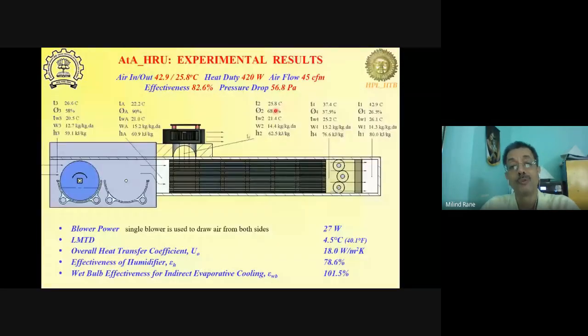Now this cooling, what we just saw here, was free, because this is simply taking the exhaust air and recovering the availability in the exhaust air using some amount of water here. Note that we have cooled down the air to below its wet bulb temperature here. Now, the wet bulb temperature of this air was 26.5, and the air being delivered is 25.68 degrees centigrade in this example. So that's why the wet bulb effectiveness is more than 100% in this case. And the enthalpy effectiveness, of course, in this case is close to 80%.